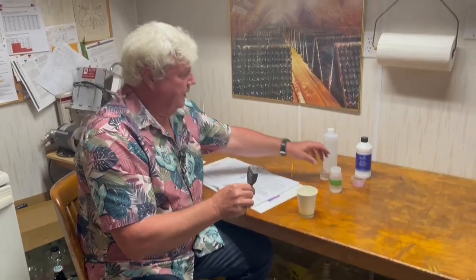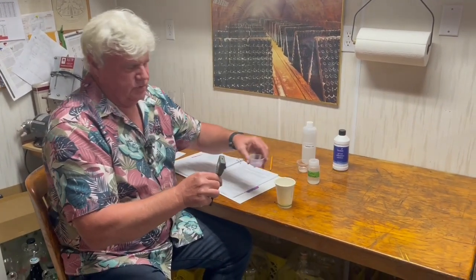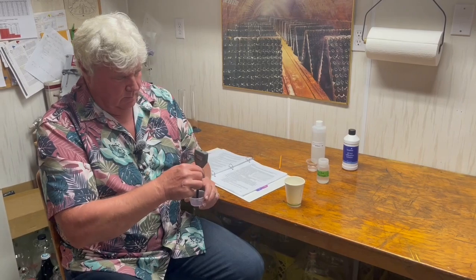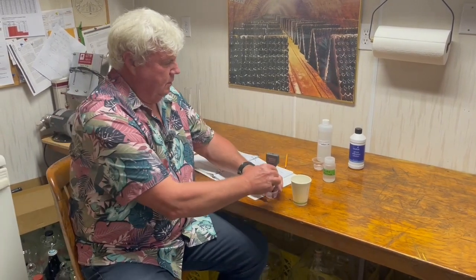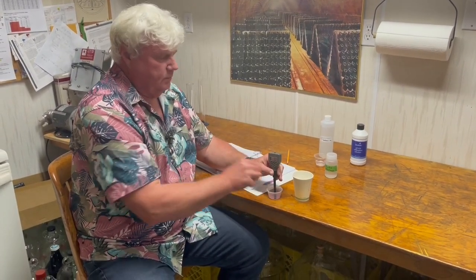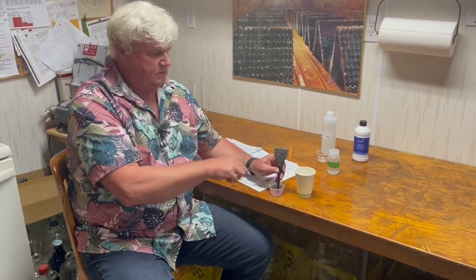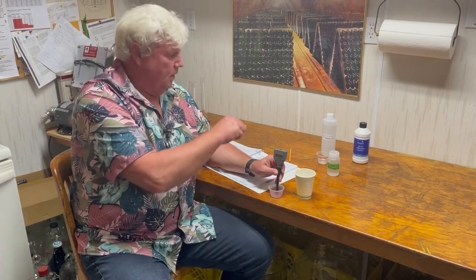So we're going to put it in the 4 solution first. Whenever you're working with your buffer solutions, always put it into a separate container, and when you're done, throw it out. Don't put it back in there, because if there's any contamination on your probe, you've now contaminated your calibration solution, and then that's no good anymore. So always get some small plastic containers and pour it in there. Once you're finished with it, you dump it out.